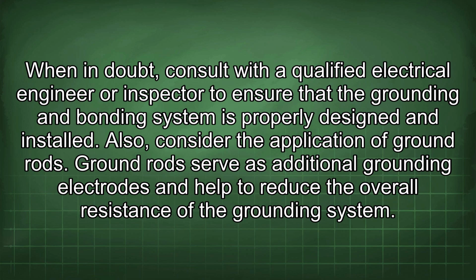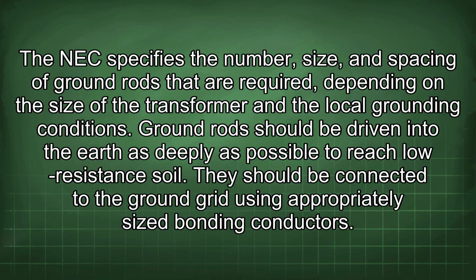Also, consider the application of ground rods. Ground rods serve as additional grounding electrodes and help to reduce the overall resistance of the grounding system. The NEC specifies the number, size, and spacing of ground rods that are required depending on the size of the transformer and the local grounding conditions. Ground rods should be driven into the earth as deeply as possible to reach low-resistance soil. They should be connected to the ground grid using appropriately sized bonding conductors.